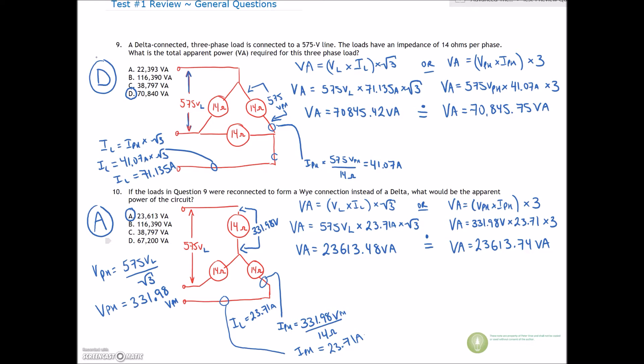Another thing to notice here is these power values. Later on we're going to look at larger induction motors and starting them up — ways to start them by reducing current and voltage, called reduced voltage starters. One prevalent in industry is the star-delta starter. The same impedance with the same line voltage draws a lot less power in Y than in delta. So the star-delta starter starts the motor in Y configuration, draws less power at startup, then once the motor's up and running we switch to delta to get full torque.